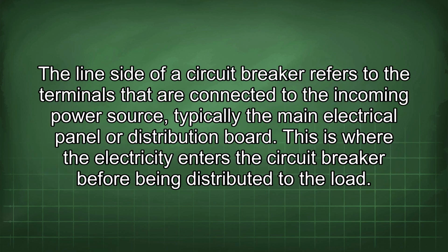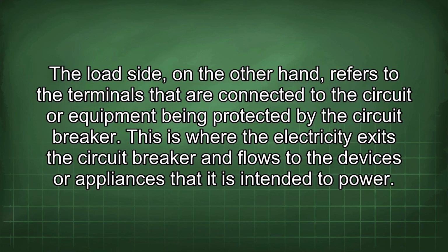The line side of a circuit breaker refers to the terminals that are connected to the incoming power source, typically the main electrical panel or distribution board. This is where the electricity enters the circuit breaker before being distributed to the load. The load side, on the other hand, refers to the terminals that are connected to the circuit or equipment being protected by the circuit breaker.